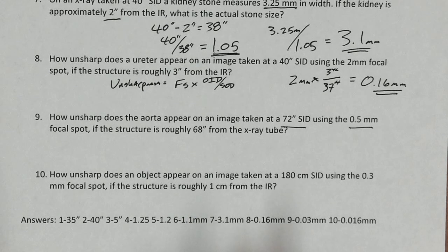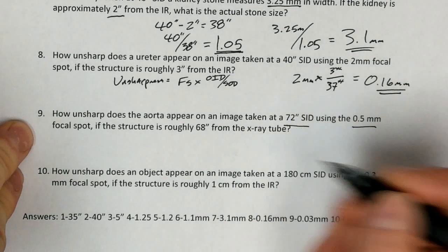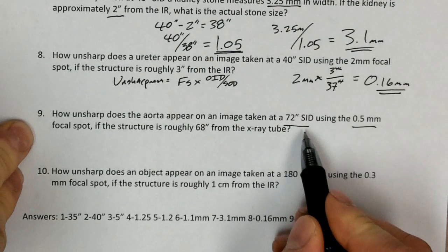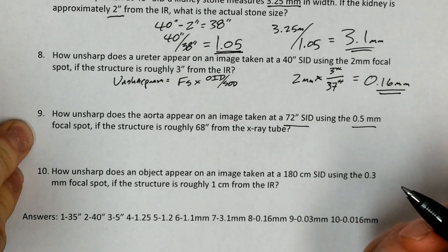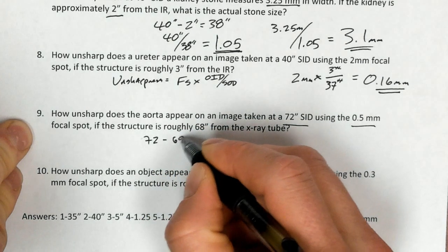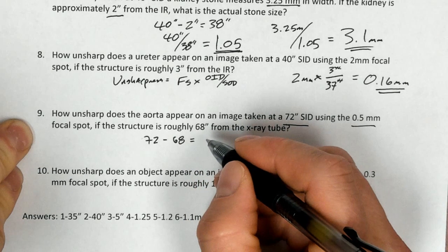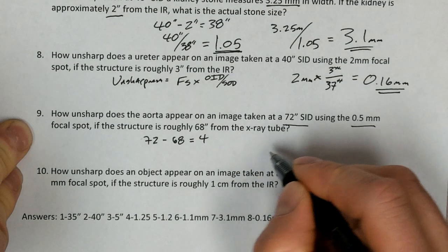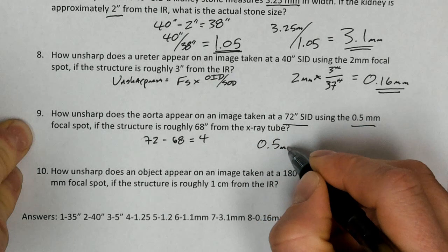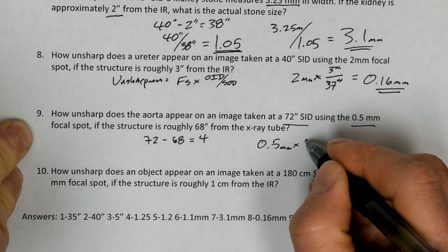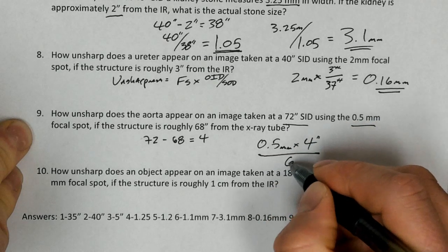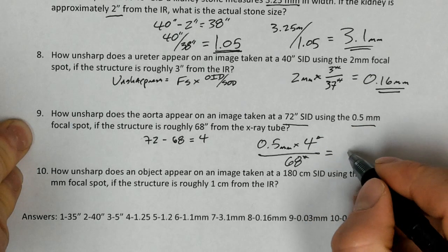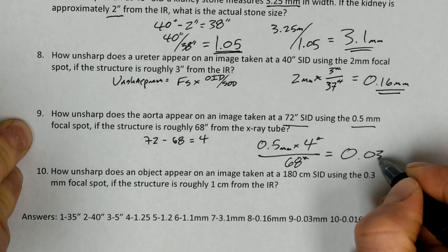So the way we'll set this one up, again, using the same formula, there's a couple of different ways we can work this. But we'll say, and they didn't give us everything that we needed. They have a SID, and they've given us a SOD here. So we'll say 72 minus 68, and that gives us 4. So the actual problem, as we should set it up here, is going to be 0.5, that's the focal spot size in millimeters, times 4, that's inches. And then we'll put that over 68 inches, and those inches will cancel out. And the end result is going to be 0.03 millimeters.